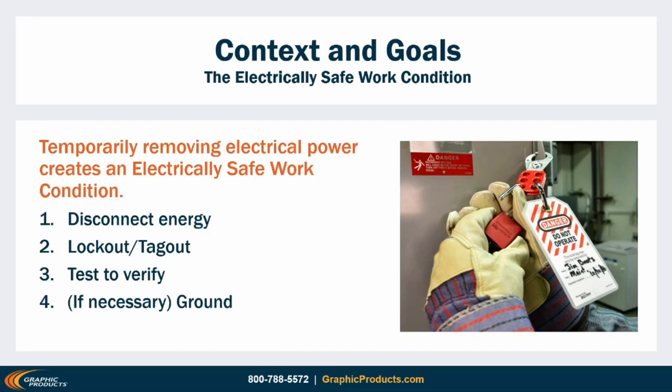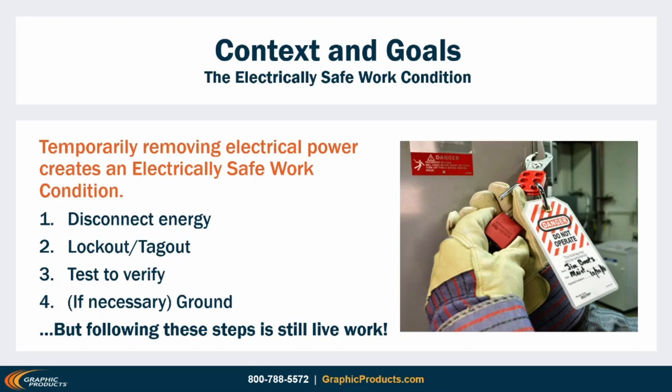There are some kinds of electrical work that simply have to be done live — troubleshooting and diagnostics, for example. But importantly, establishing an electrically safe work condition is itself live work, because the condition hasn't been established yet when you go through those steps. In the real world, some kinds of live work, such as establishing an electrically safe work condition, will always involve the potential for arc flash — that is, an arc flash hazard.